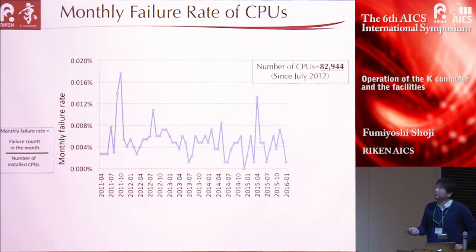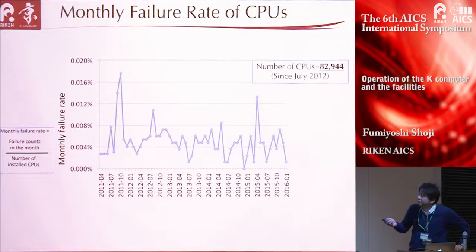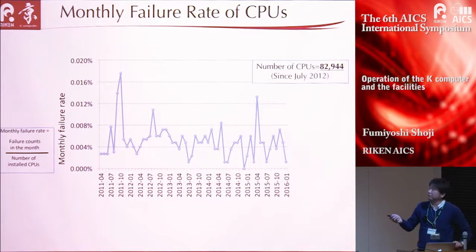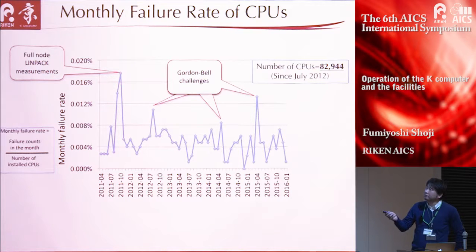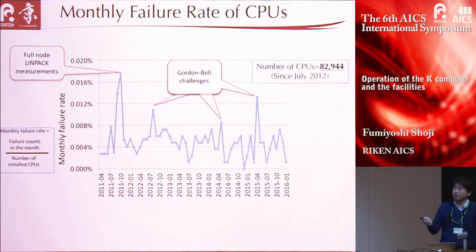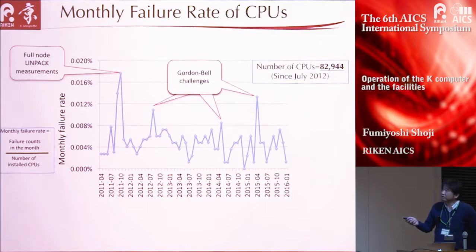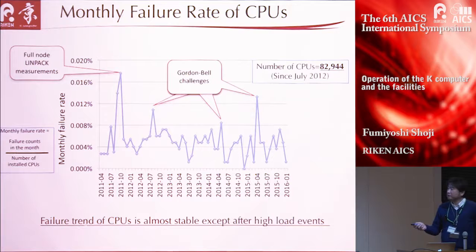I will show you the failure rate of major parts. This is the monthly failure rate of CPU, defined as failure counts in the month divided by the number of installed CPUs. You can see some spikes that correspond to high-load events—for example, the full-node LINPACK measurement where the K-computer achieved over 10 petaflops, and points corresponding to the Gordon Bell challenge. The failure trend of CPU is almost stable except after high-load events.